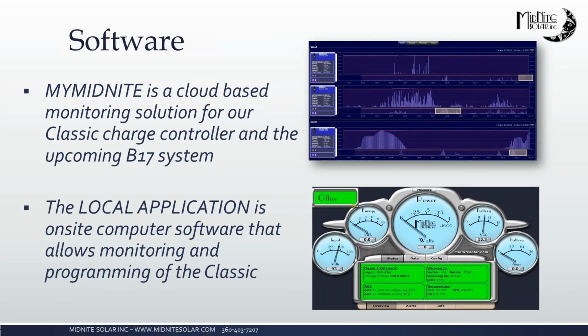I will say that all the Classics, except for the SL, will work with this because the SL does not have Ethernet, as Sue pointed out. All of the Classics do speak Modbus. So if you want to do third-party stuff that's an openly published protocol, you can ask the Classics and the Classic SL's Modbus questions all day long, either by RS-232 or by TCP/IP. So if that's something of interest to a customer, have them reach out to us and we can get them the information for that.